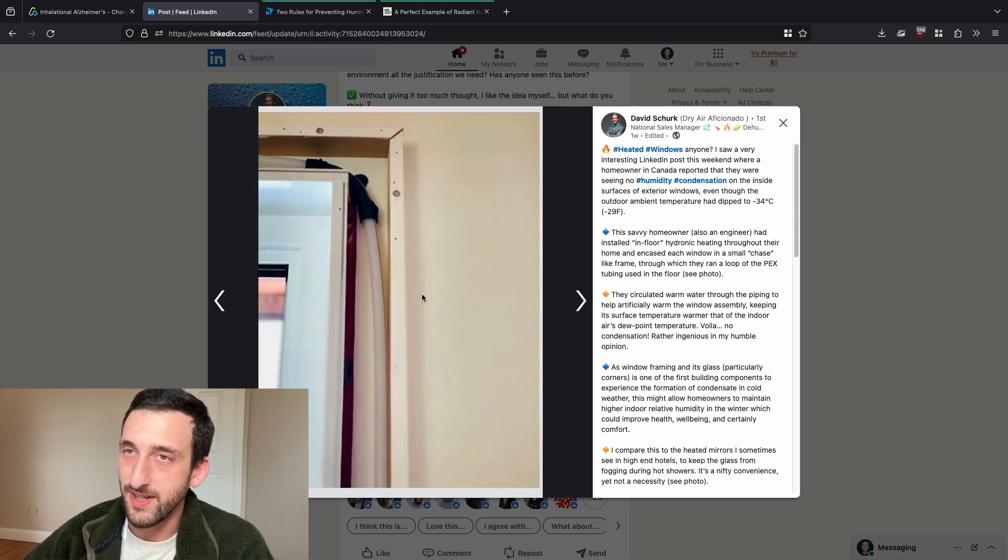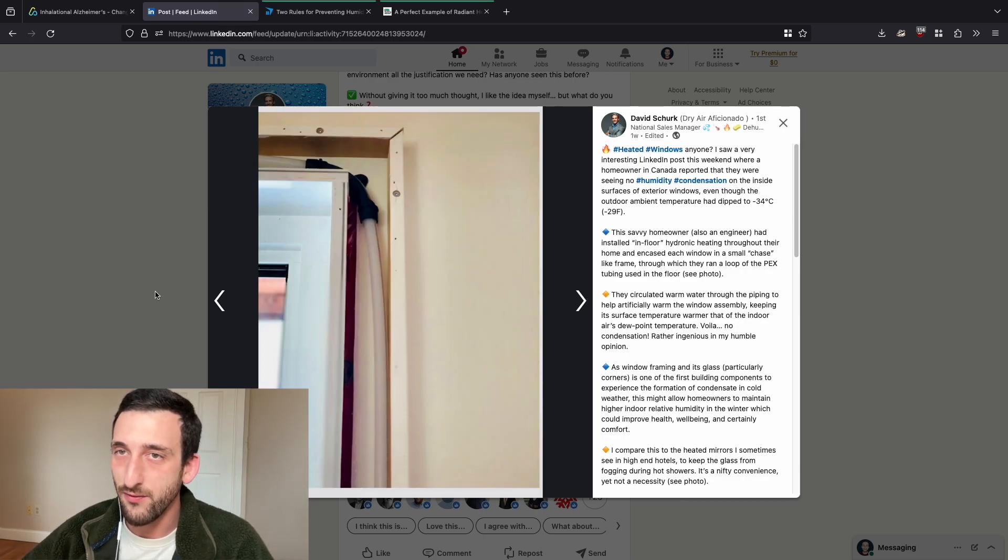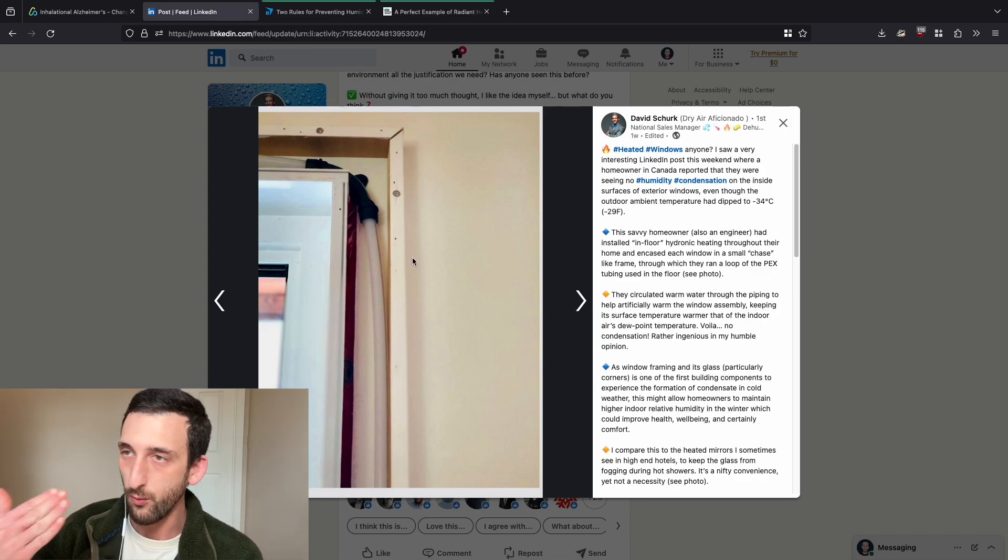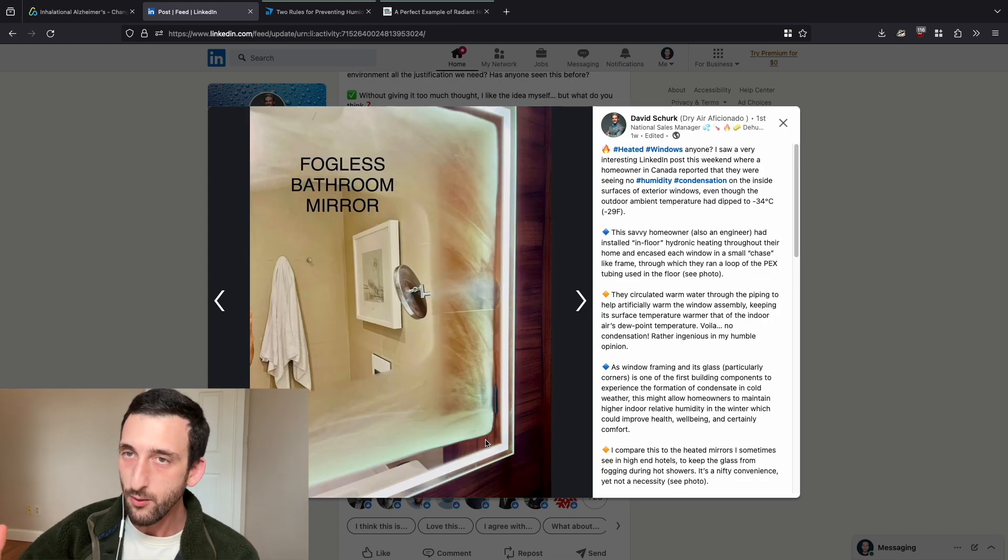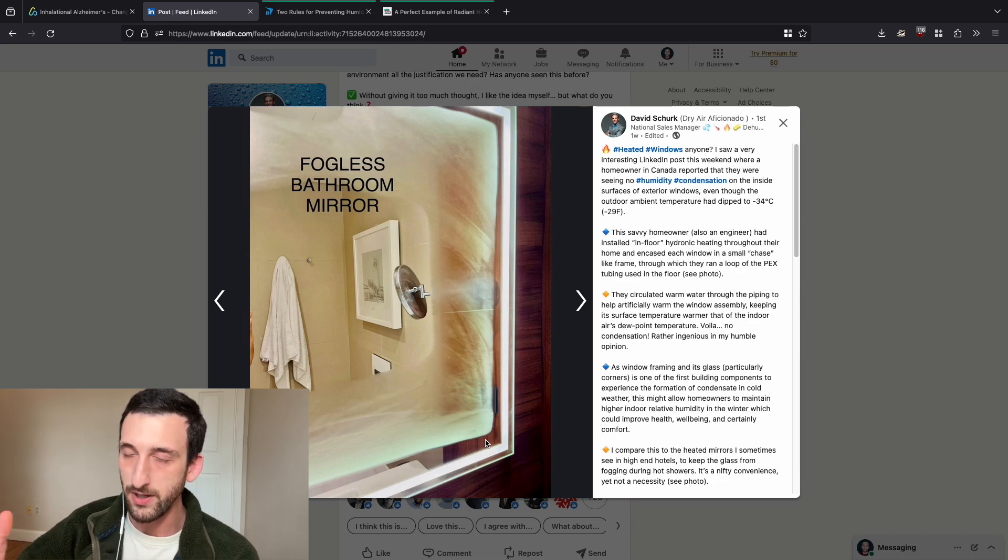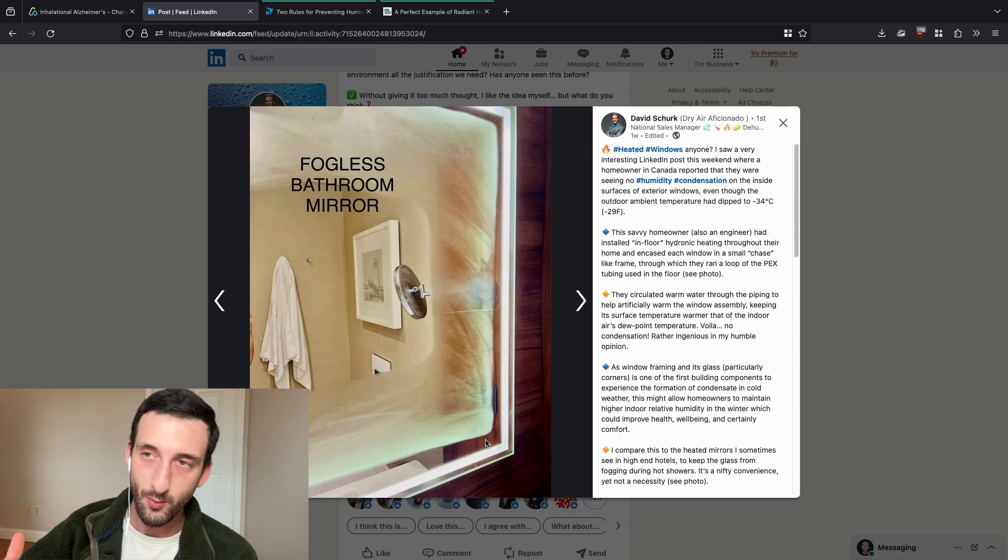So what this person did is they ran PEX tubing around the framing of the glass. They pumped warm water through that piping. The idea was basically to heat the glass above dew point temperature, which prevents condensation from forming on it.